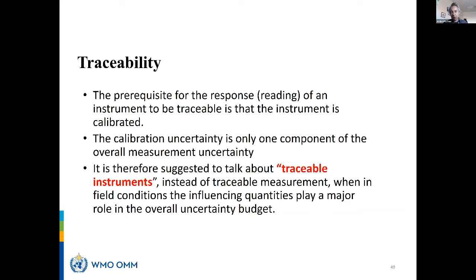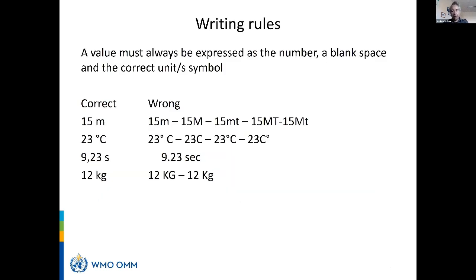So I prefer to talk about a traceable instrument, but don't say it to PTB colleagues, please, because this is my point of view. I like to say the instrument is traceable. The VIM says that the measurement result is traceable. I say the instrument is traceable because it is calibrated with respect to an instrument which is. But the overall measurement result, to me, should include all the environmental conditions. Okay, I think I will stop here.